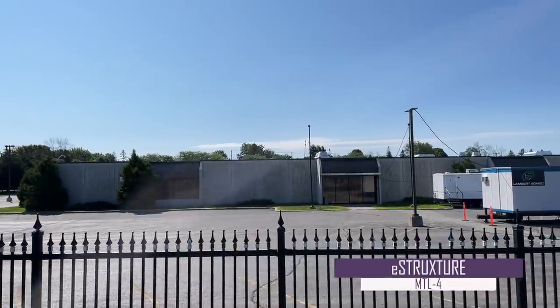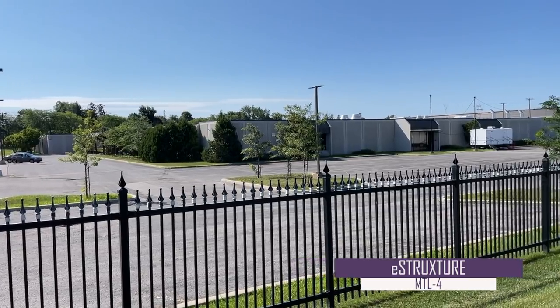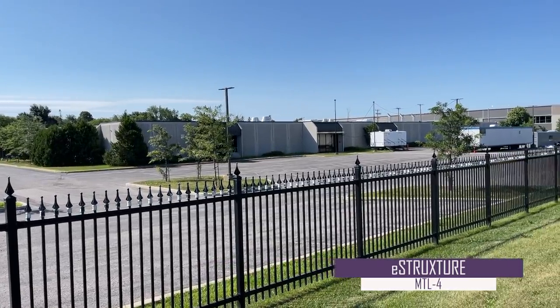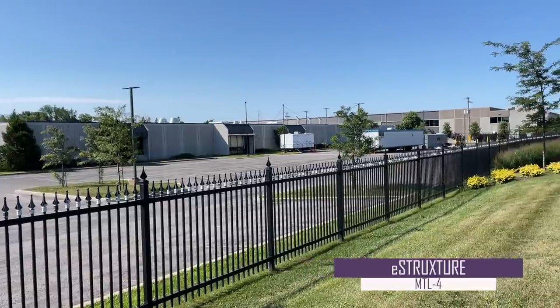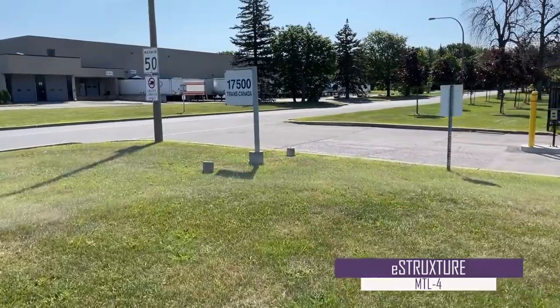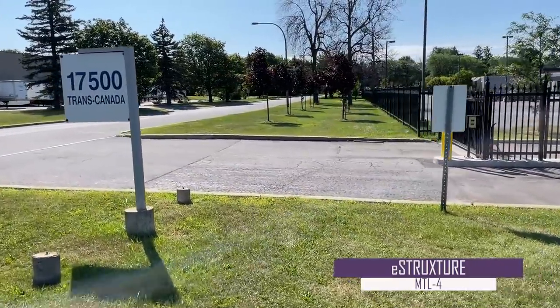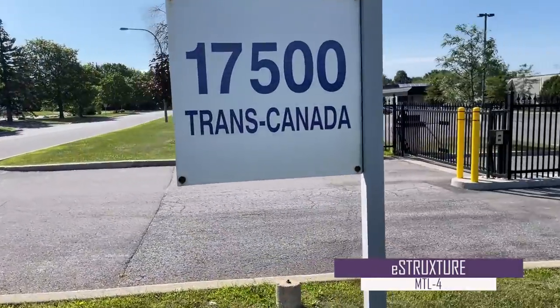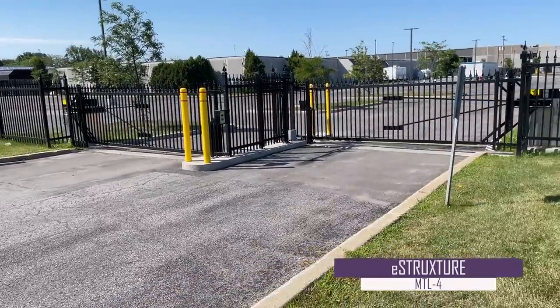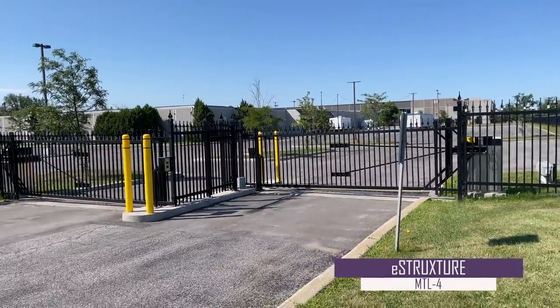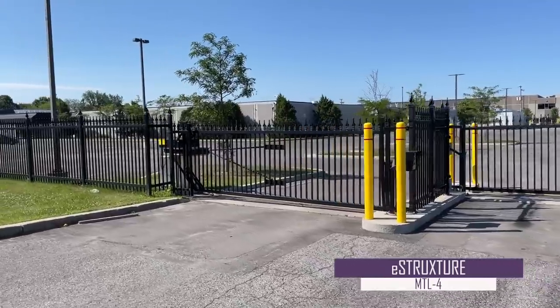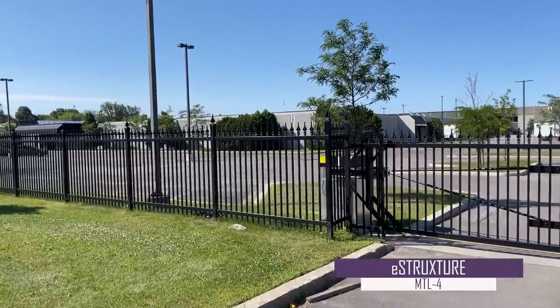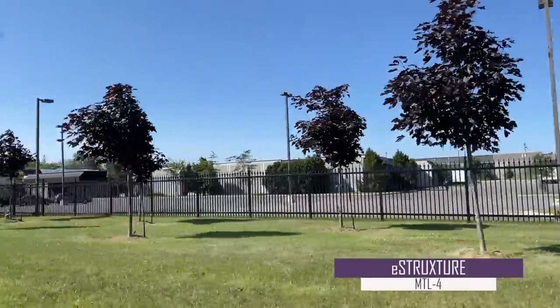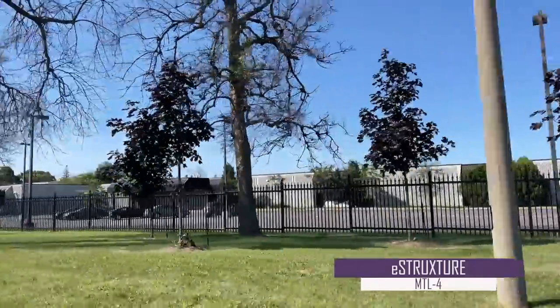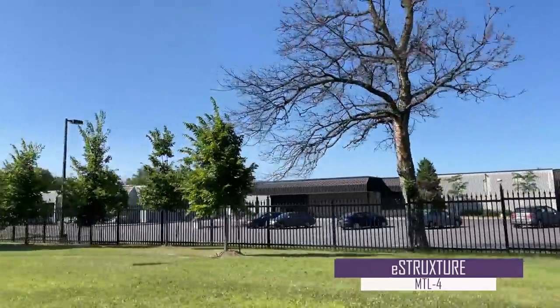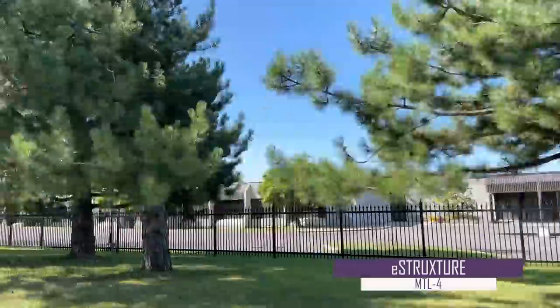The entire site has a controlled perimeter access barrier, spanning over 500 feet on each of its 4 sides. MTL4 comprises 103,000 square feet of total space and has the ability to grow to 16.5 megawatts of power capacity over 4 data halls. Currently, it has a primary utility feed of 4.5 megawatts. Additionally, the facility is diversely fed from 2 different power substations. Finally, in terms of connectivity, MTL4 is network neutral, with access to 9 carriers through 2 diverse meet-me rooms.